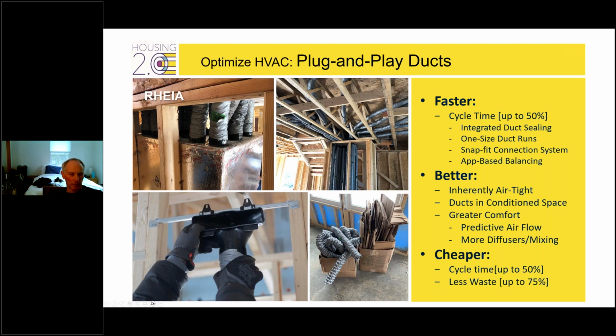Each duct does about 20, 25, 30 CFM of airflow. So if a room needs 60 CFM, you run 2. If it needs 90, you run 3. And you basically have great mixing. You have airtight construction without having to factor in the quality of the workforce. It goes in airtight just naturally, and it's much simpler to lay out.